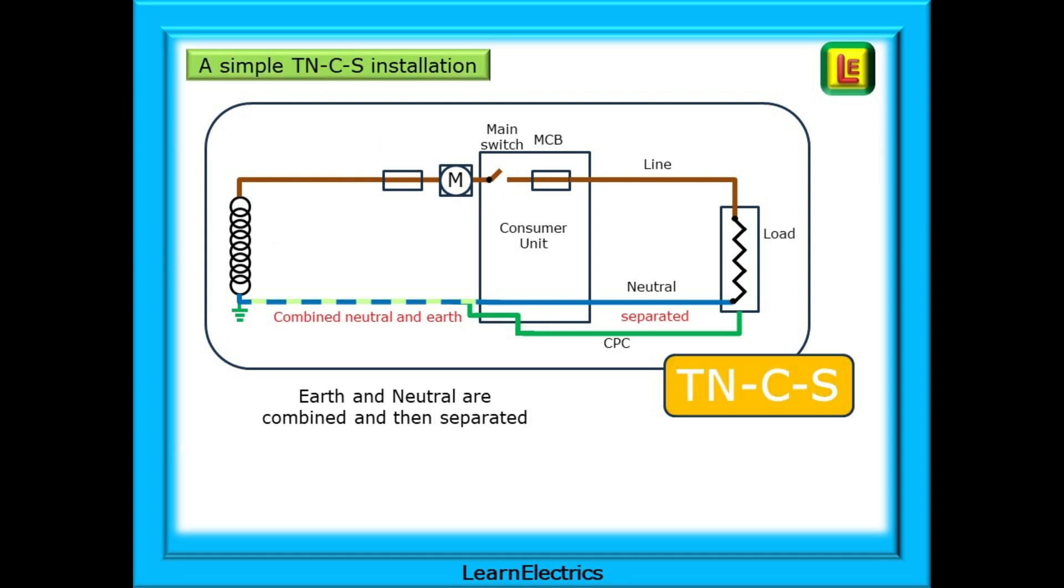Compare this to a TN-C-S system where the cable from the transformer to the building has the earth and neutral combined together and at the intake position just before the consumer unit they are separated into two individual conductors, earth and neutral. We call this system TN-C-S - earth and neutral combined and then separated. From the consumer unit the systems are the same.